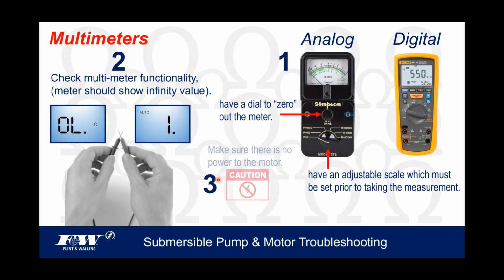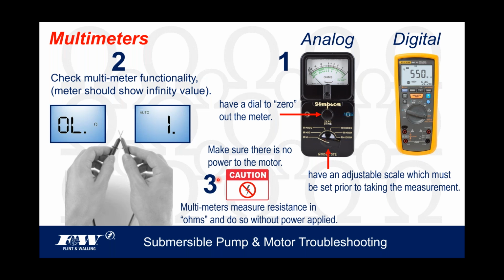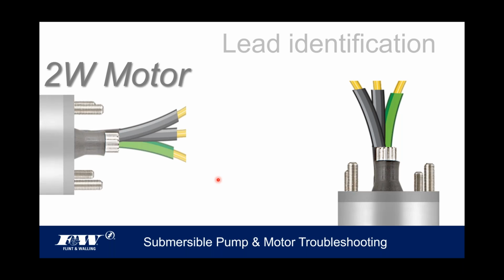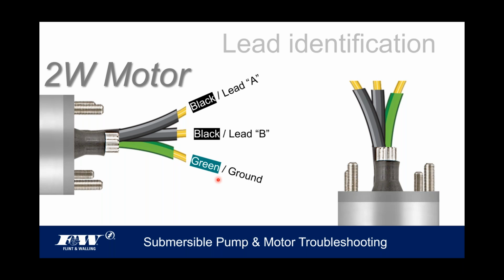So this is a no-brainer here, but I can't fail to bring it up. Make sure there is no power to the motor, as we're going to do some tests to determine what's wrong with the motor. All right, so here we go. When it comes to submersible pumps, we've got 2-wire motors and we've got 3-wire motors. A 2-wire motor is simply going to have 2 black leads off of it and a green ground. So we can refer to those as perhaps lead A, lead B, and of course the green ground.